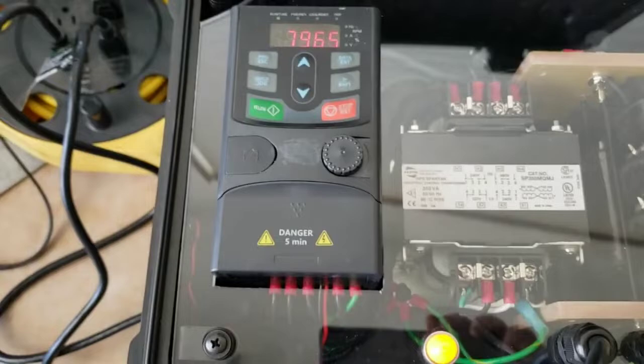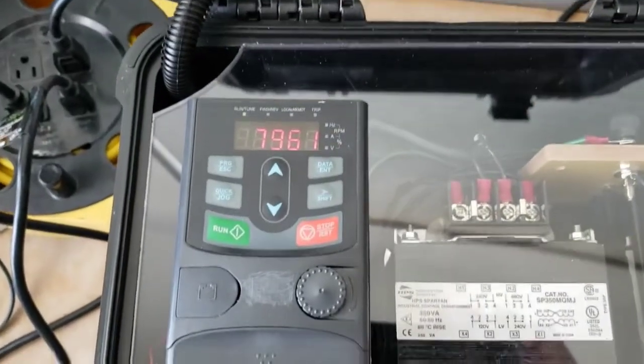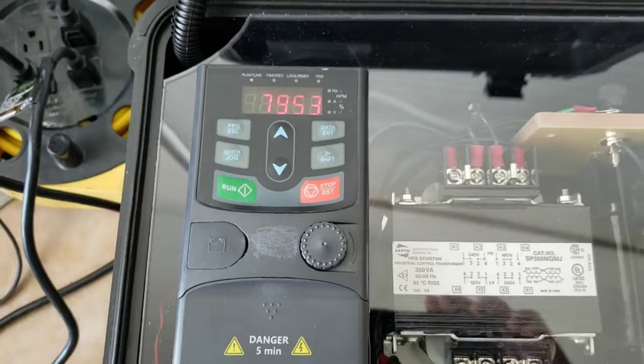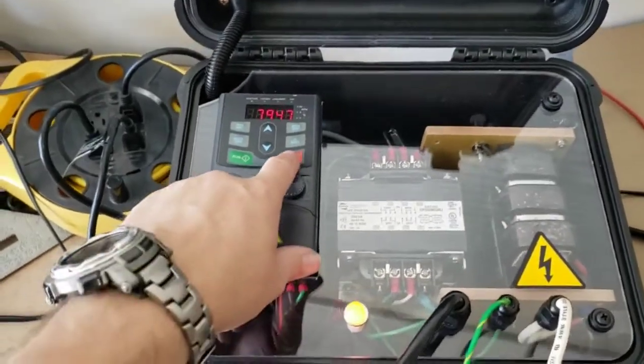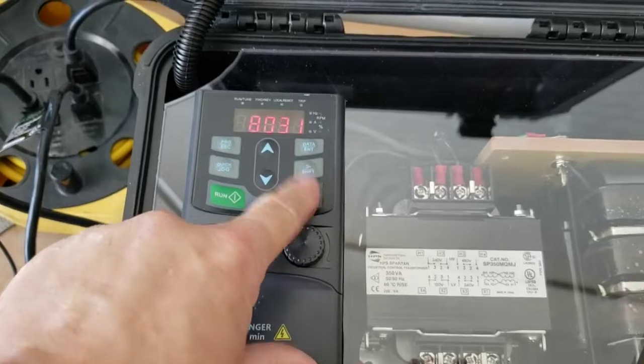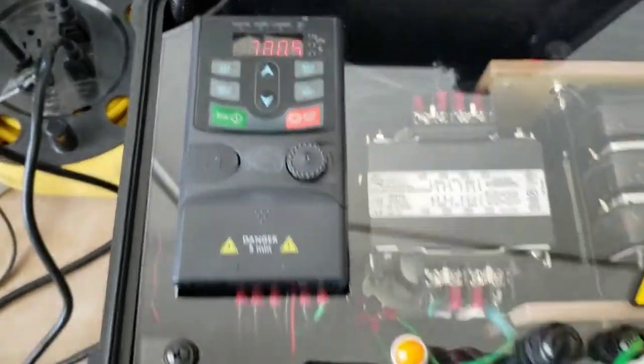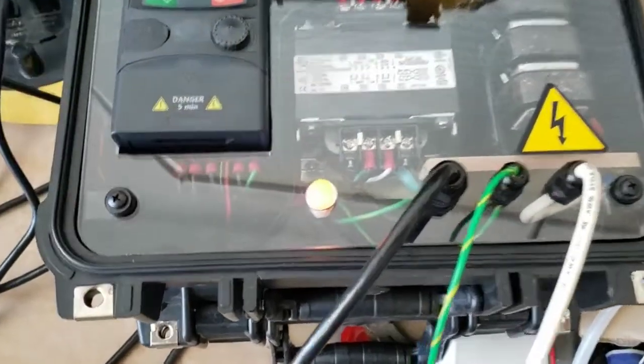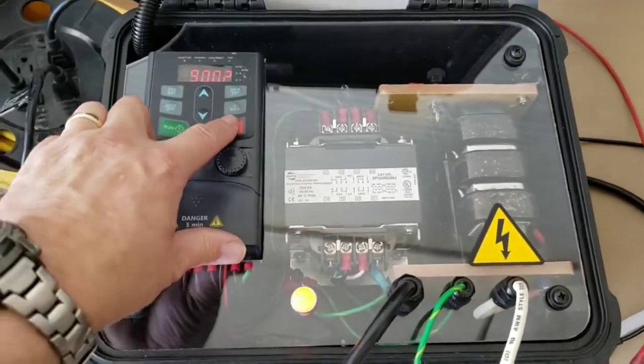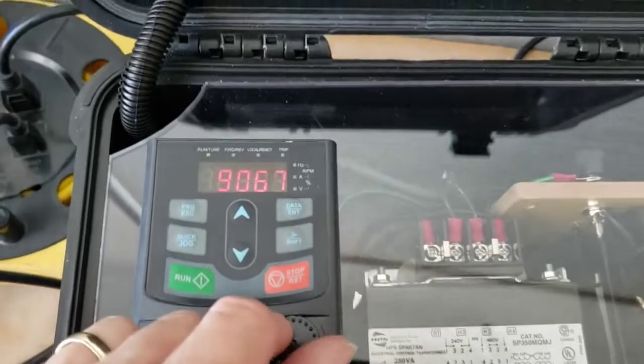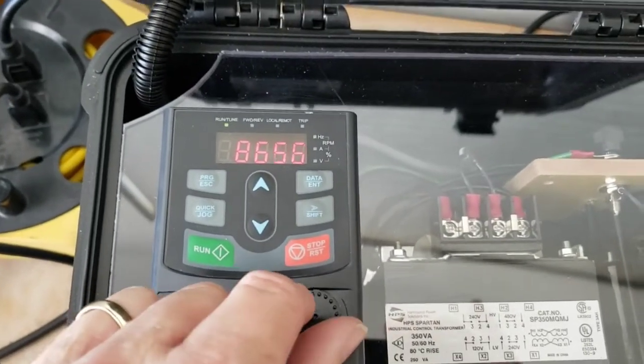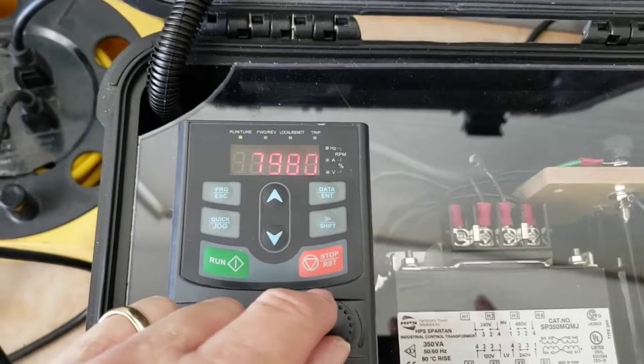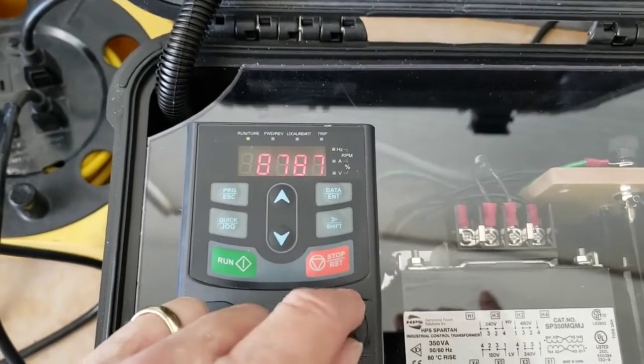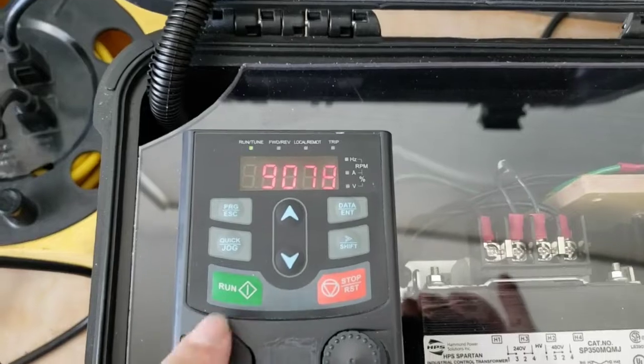So if you had a bad cell, it would hang up at a wrong frequency, or it wouldn't finish that sweep and find a good frequency. When you want to stop the test, just push stop. Also, if you've noticed, when I had it on, the orange light illuminates on the panel. That's just to indicate that you've got high voltage going. But now that I've turned it on a second time, it's not doing that sweep. So it only does that sweep for one cycle of the power. Now I can just go to whatever power I want. See how as I turn it down, the frequency goes up.